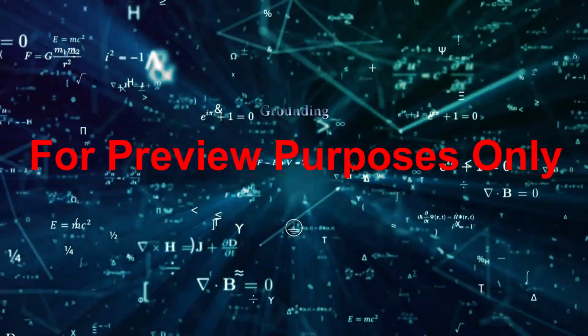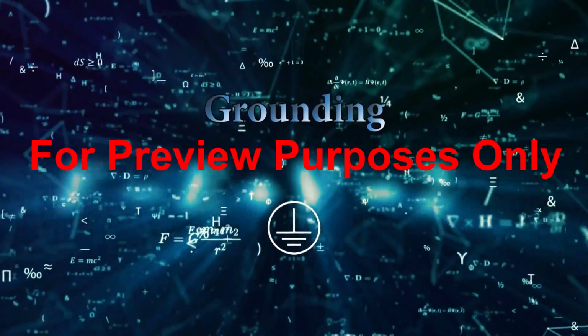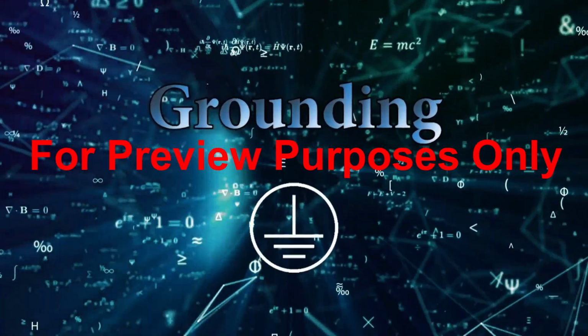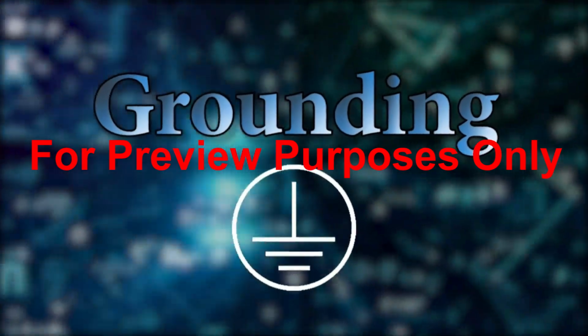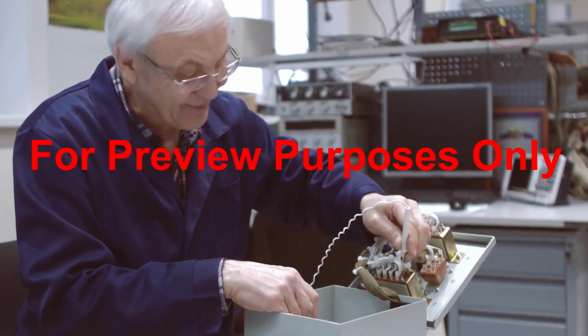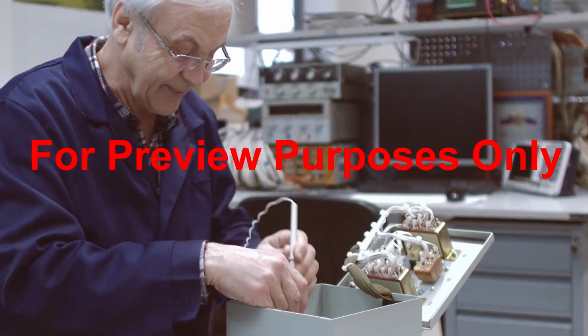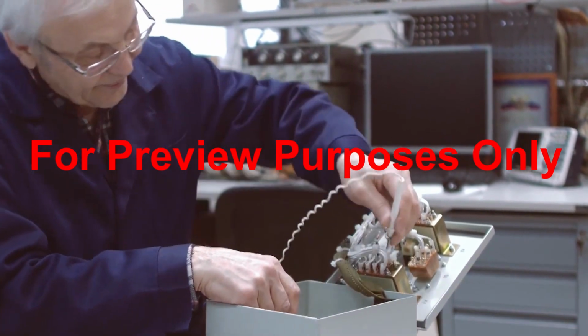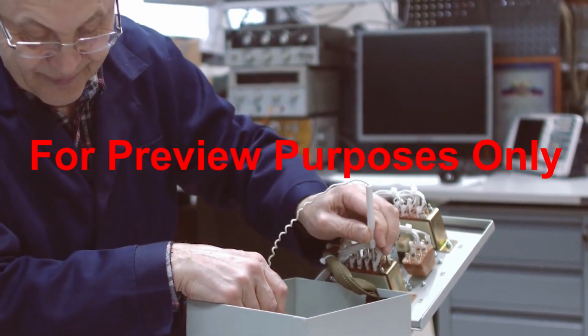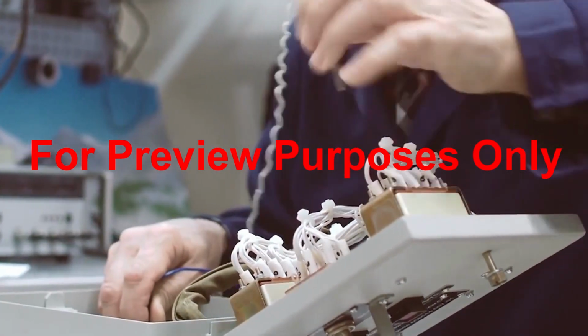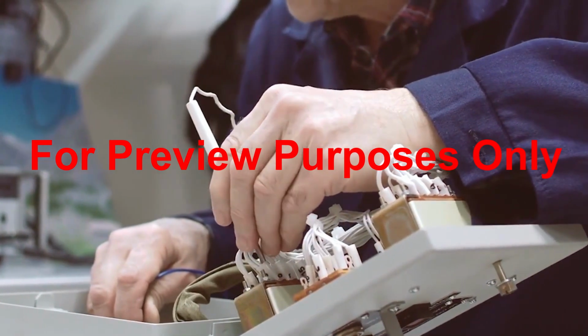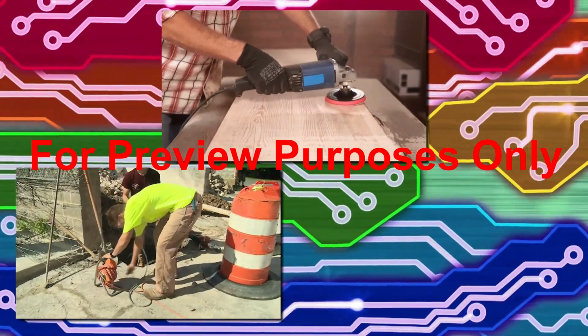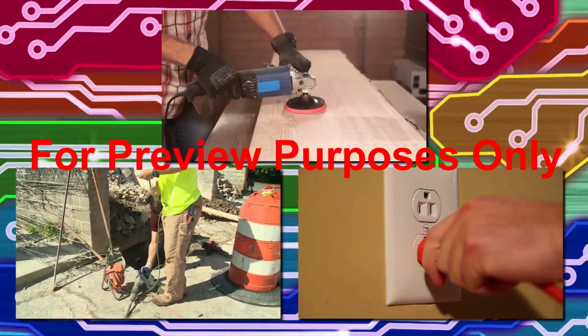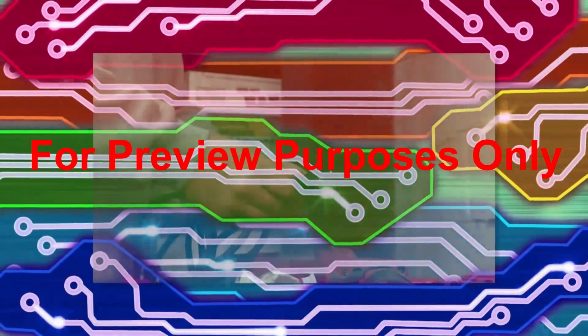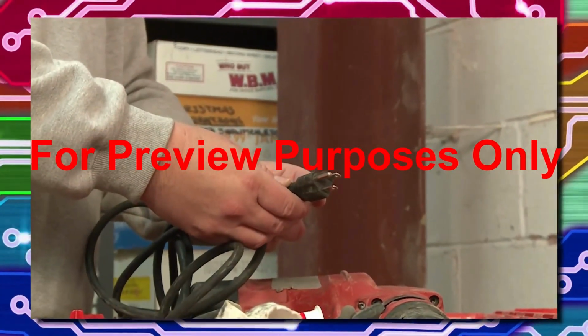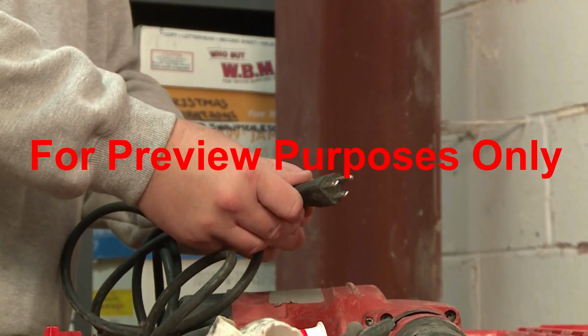To understand how these two options reduce electrocution hazards, it helps to know a little more about grounding. One way to protect people from being electrocuted by electricity that is trying to jump to ground by going outside of the equipment that they are using is to provide a safe path to ground on the inside of the devices. Power tools, cords, and receptacles that have this feature are called grounded equipment and will always have 3 prongs on their plugs or 3 holes in the receptacles.